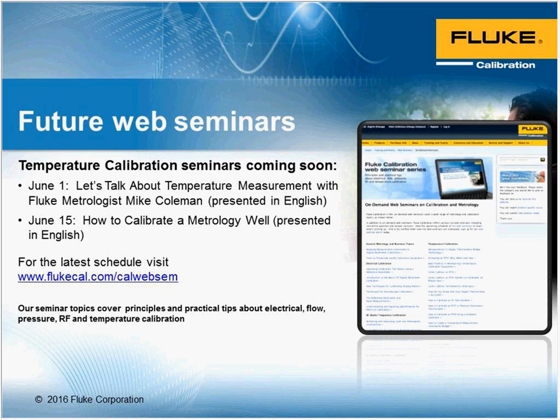From everything that I've been taught, if you can immerse a probe, even a surface probe, if you can get full immersion, say in a dry well or a bath, it's going to net you the best results versus a surface operation. But again, that's not always possible. So sometimes, like you're doing here, you do have to get creative. The biggest thing to consider when you're coming up with these techniques is to ensure that the process can be repeated. So just make sure you're getting good consistency and good repeatability in your process.